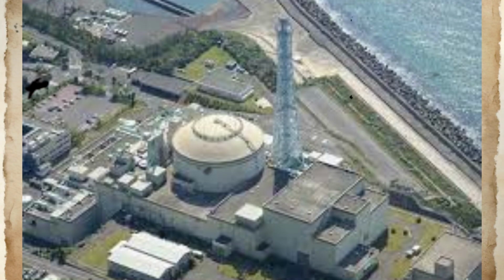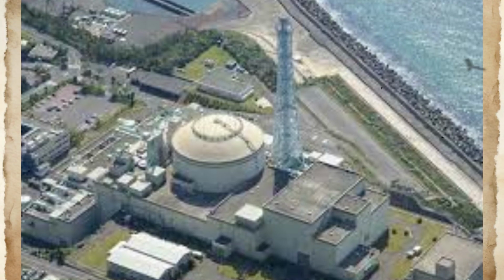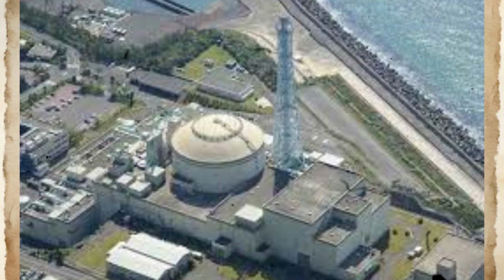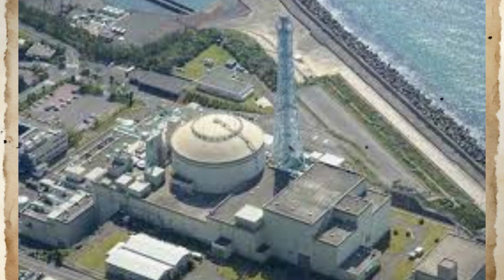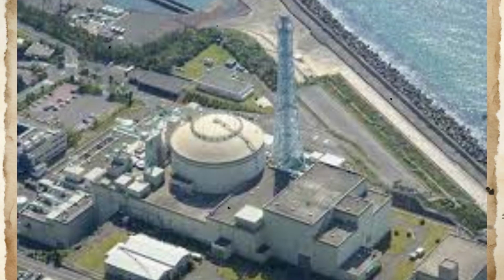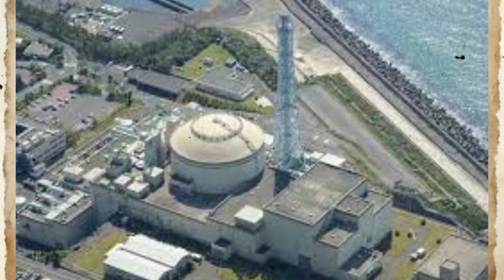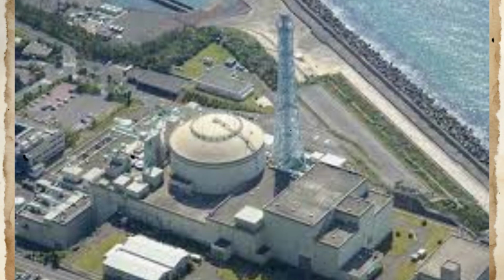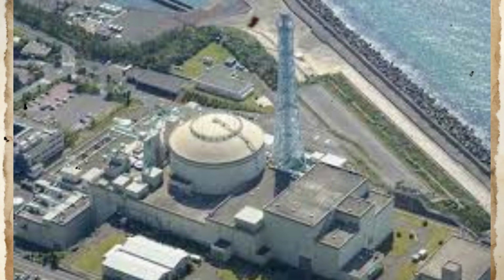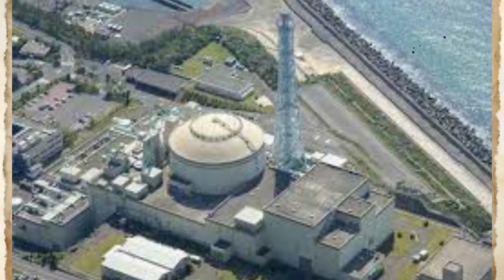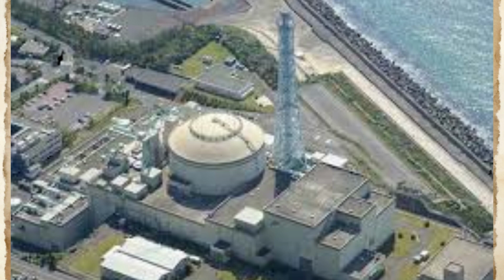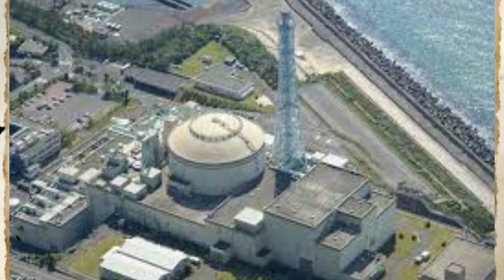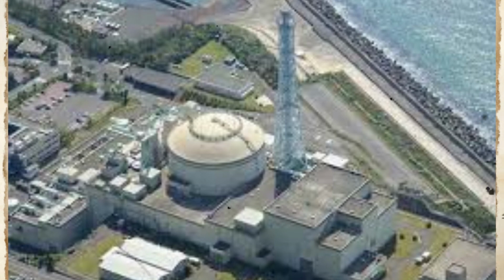The assumption proved incorrect when secondary system component failure initiated a sequence that required emergency response procedures and ultimately led to manual reactor trip. The alarm system design had not anticipated that small component failures could escalate through operational complications to require emergency actions. Control room ergonomics further reinforced the thermal management focus.